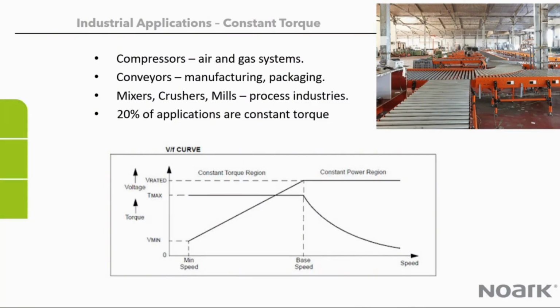Constant torque, however, which consists of about 20% of the applications, compressors, conveyors, mixers, they require constant torque and energy consumption throughout all ranges. So it's more of a linear progression of energy versus speed, because you're always going to need to overcome that torque.